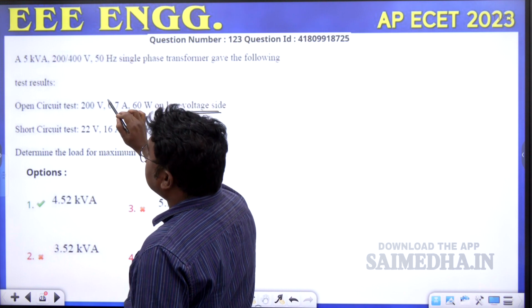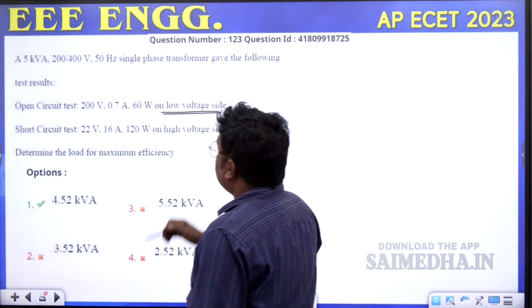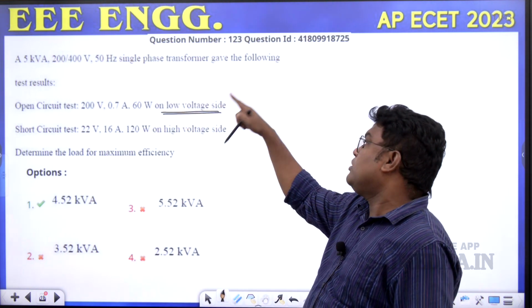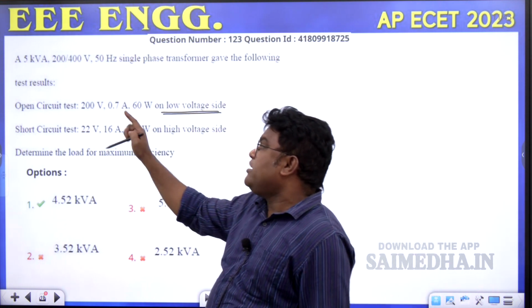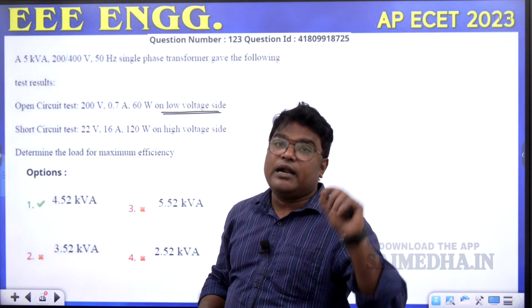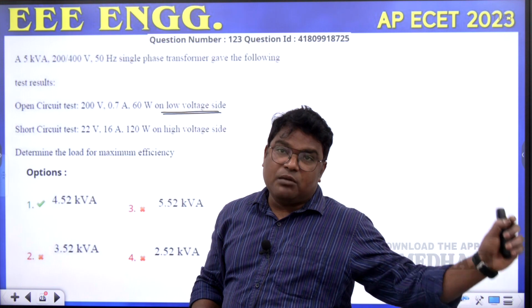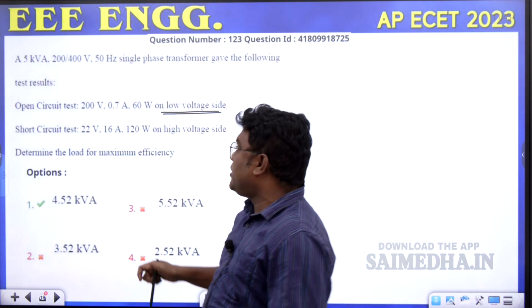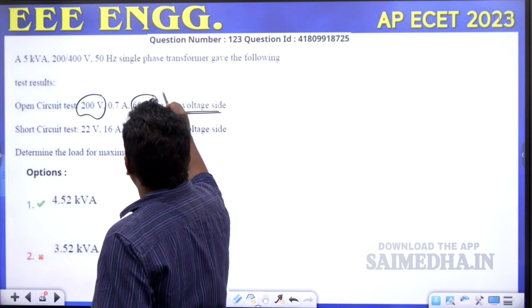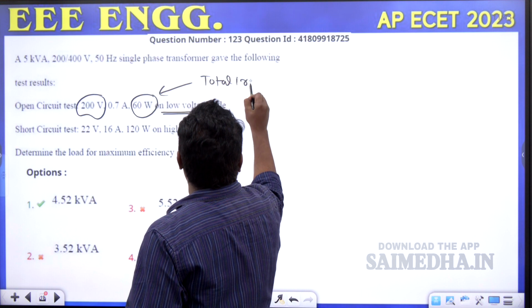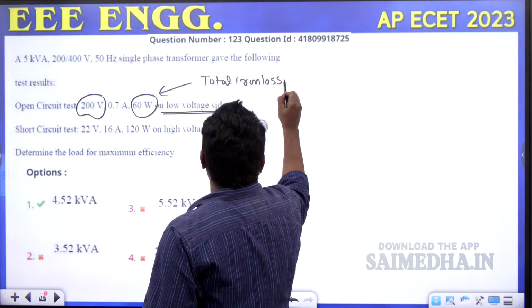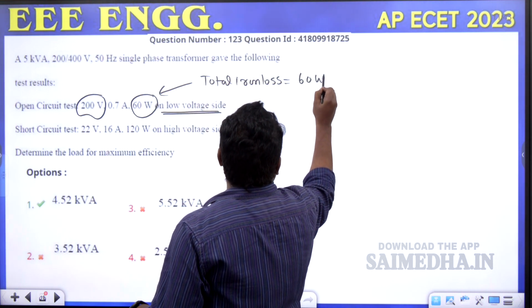So in this case, here it is mentioned that the open circuit test is conducted at rated voltage condition, on the low voltage side. Normally, the open circuit test is conducted on the low voltage side of the transformer at rated voltage. So this rated voltage is mentioned here, and these are the total iron losses of the transformer. So this iron loss is equal to 60 watts.